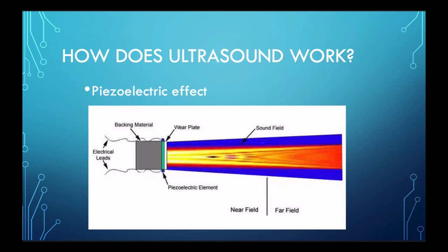We have piezoelectric material, or crystals, within these probes. When electric current is applied to these piezoelectric crystals, they vibrate, and the vibrations then produce sound waves that travel outward away from the probe. As these waves travel through and bounce off of structures, some of these waves will then be transmitted back to the crystals. The same crystals then receive these returning sound waves and vibrate, and their vibrations then result in electrical current that's converted into digital images.